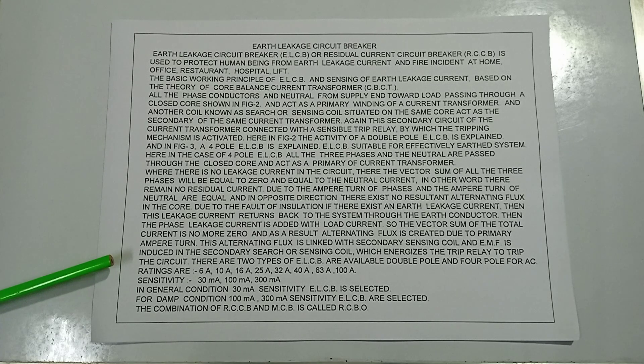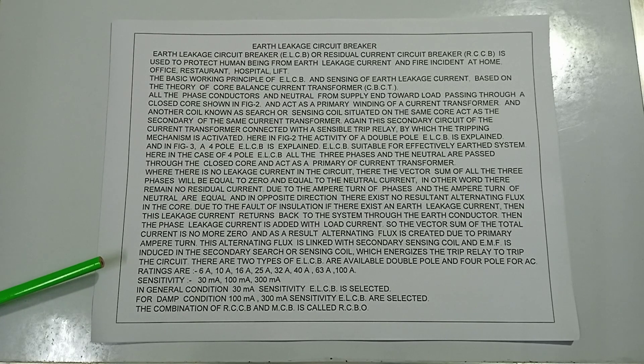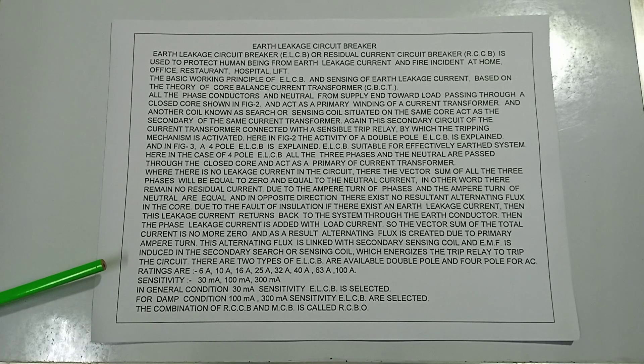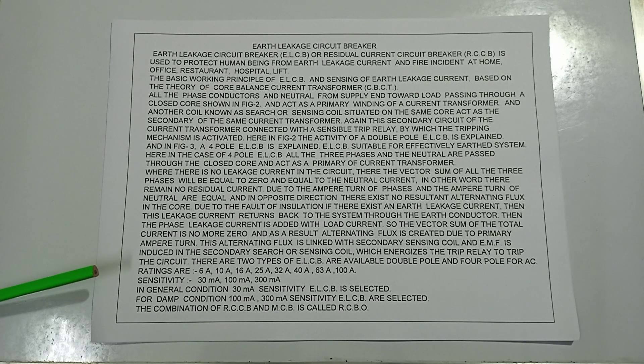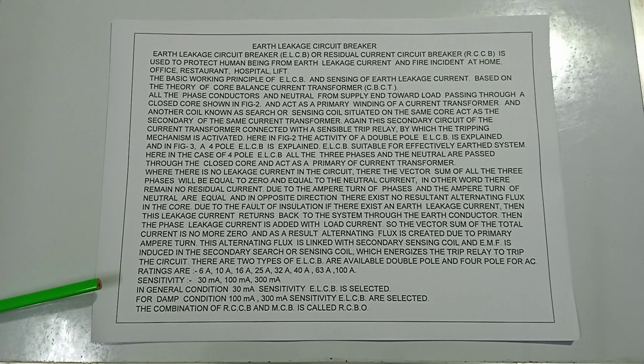There are two types of ELCB available: double pole and four pole, for AC use. Current ratings are 6A, 10A, 16A, 25A, 32A, 40A, 63A, and 100A. Sensitivity ratings are 30 mA, 100 mA, and 300 mA.